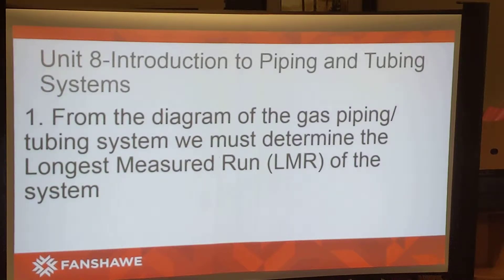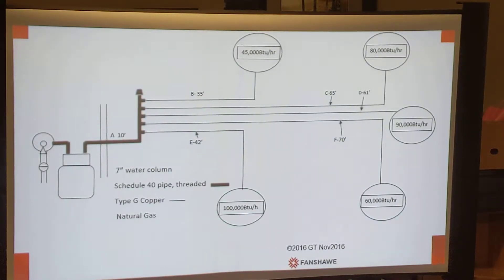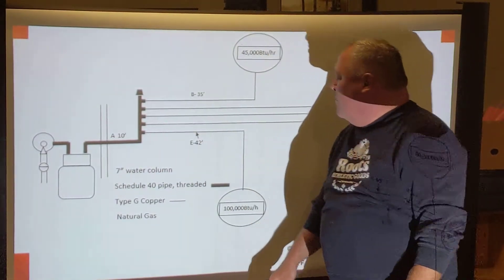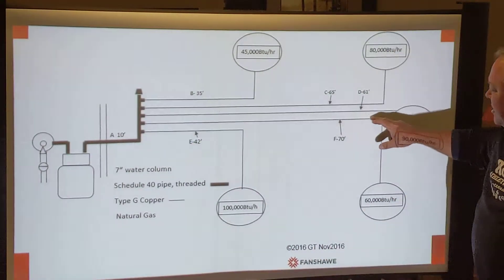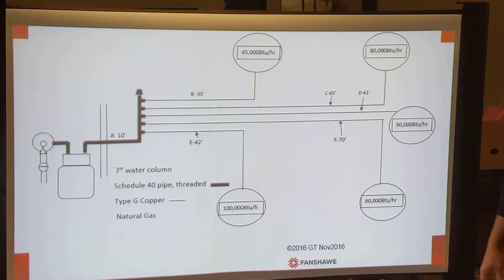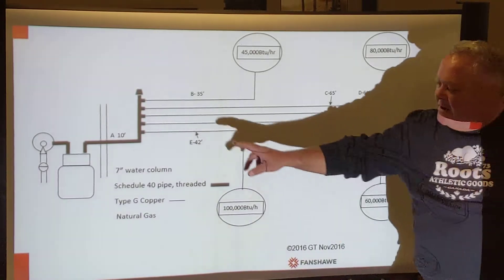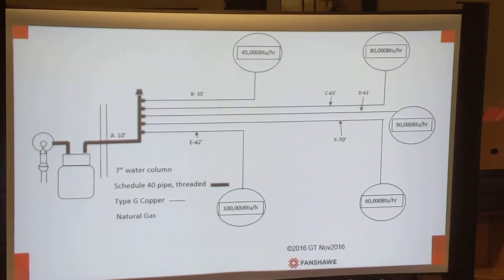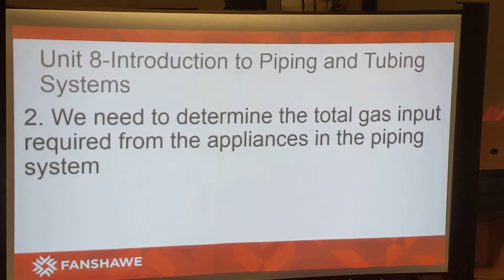When we look at this application, we have the longest measured run measuring from the outlet of the gas meter. We have a 10-foot section of schedule 40 pipe and also a 70-foot section of tubing to the 60,000 BTU per hour appliance. Section F, which is 70 feet, plus the 10 feet are what we're going to use to determine our longest measured run, so our LMR is going to be 80 feet.